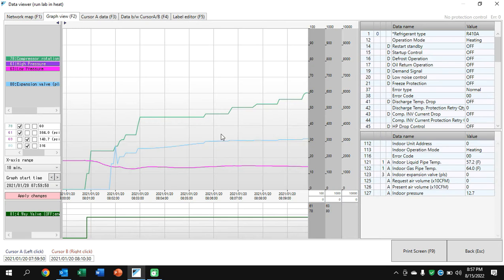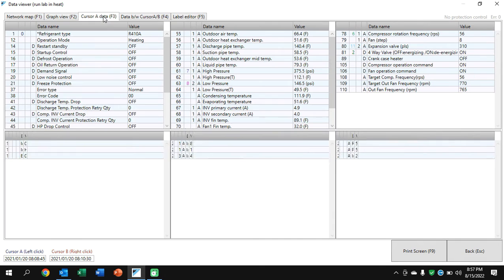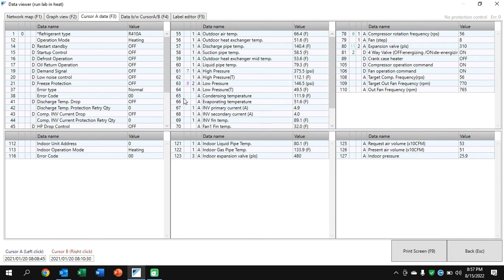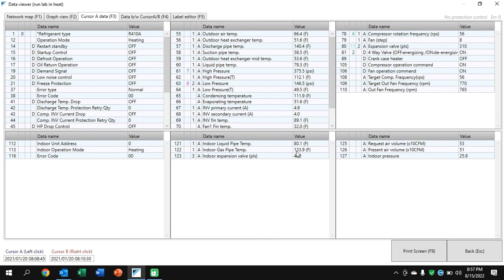This is a heat mode fit. I want you to be able to just get a peek at some numbers. And we'll go up. And we'll open the data here. And then we'll see. We'll find a spot along the data line where we have data. And we'll go back to the cursor data. And we'll see the indoor expansion valve at 480 wide open. And the outdoor one is modulating. And this stays pretty wide open during a heat mode. Pretty standard heat mode. You'll see in the top right actually says operation mode heating. And again, we'll see our pulses change. We'll see our pulses outside be modulating and the ones on the indoor be wide open. We'll also see the pressures of course change on the indoor section line as well.